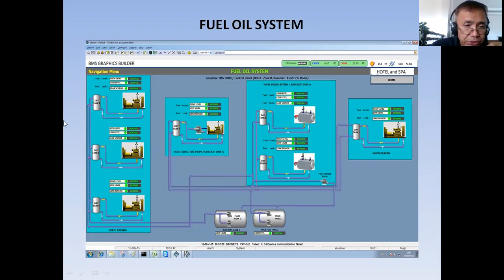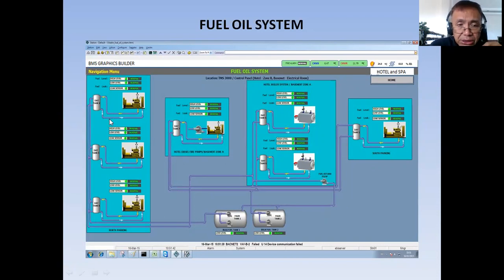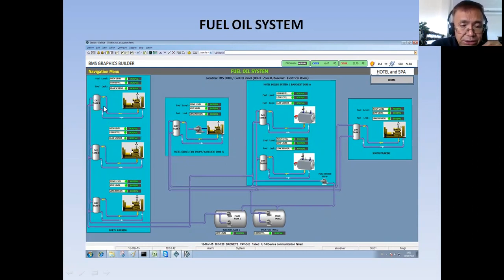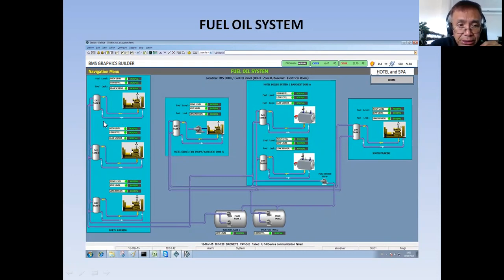Now, what are the points being monitored in the data? Since this is a fuel system, we are just monitoring the high level and low level of the day tanks. There is also one leak sensor. As to how they provide the leak sensor — these day tanks, I think these are double-walled, and sensors are being installed in the outer wall of the tank. Since it is double-walled, they will put a leak sensor inside of the outer wall.